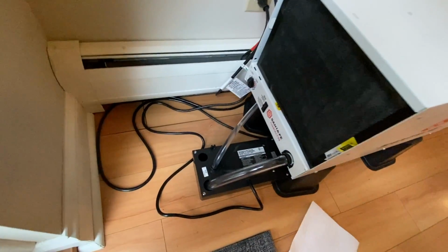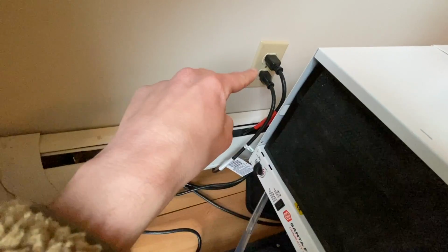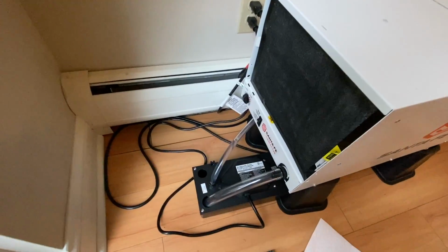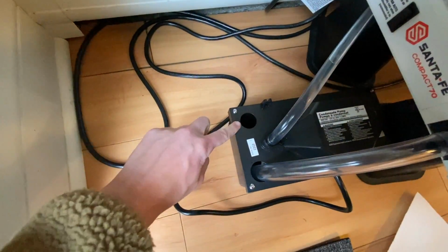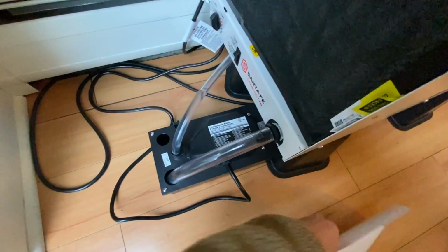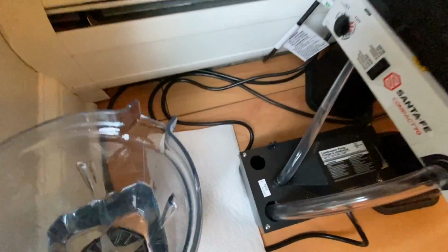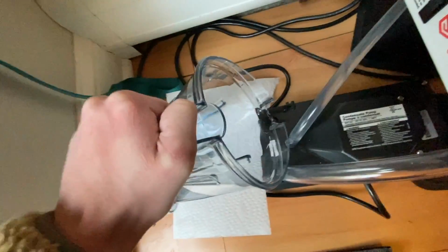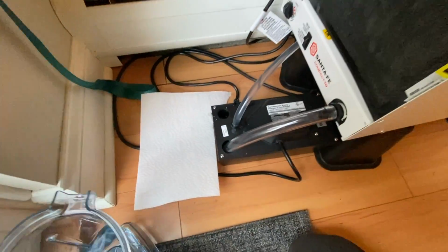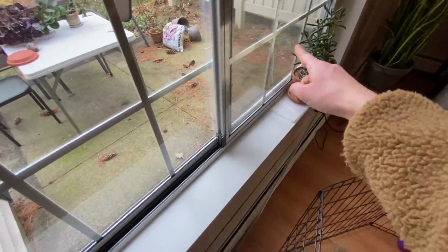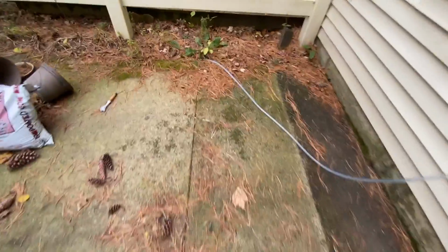When you have your condensate pump all set up and plugged in, definitely don't forget that, we're going to test it with some water. So let's pour some water into this hole right here. And make sure you have that drainage tube set up so the condensate pump pumps water where you want water to be, right? Not onto your floor. And there we go. That's the sound we want to hear. We want to see water rushing through the tube. And let's follow it to where the water goes. So it goes, as I said, out that window. And let's go see if it's working properly. So here's the tube.